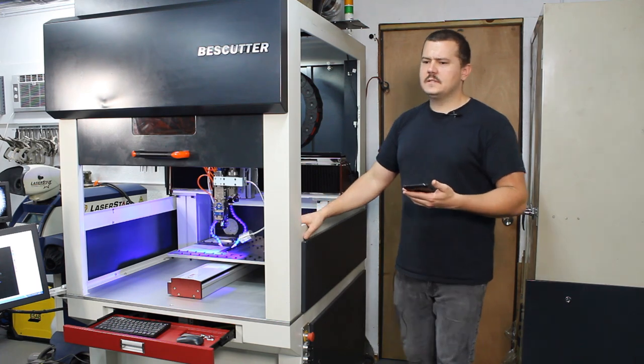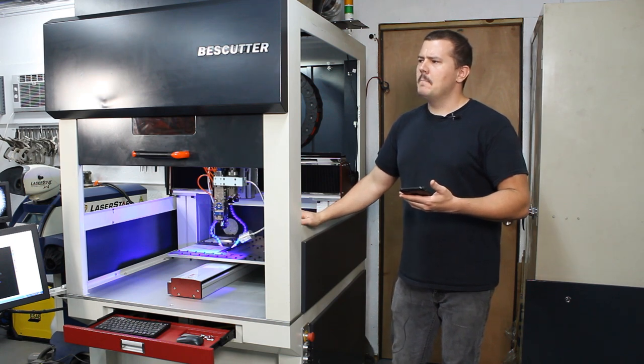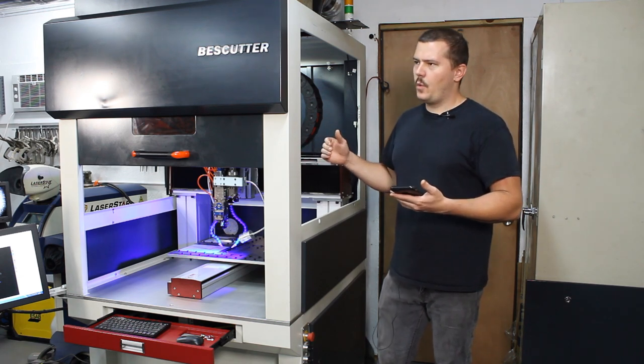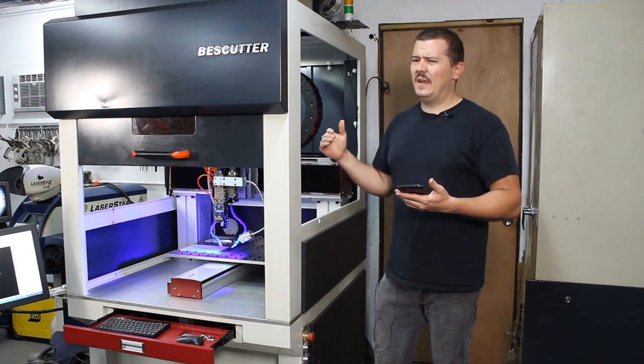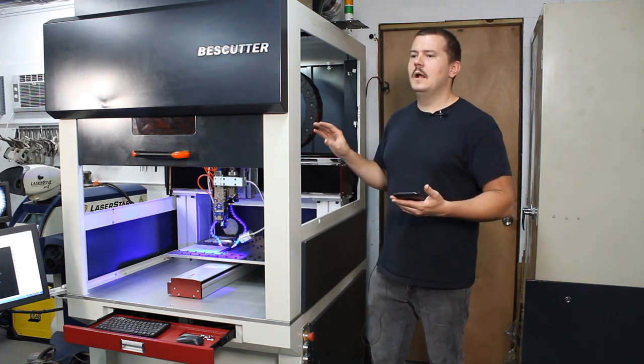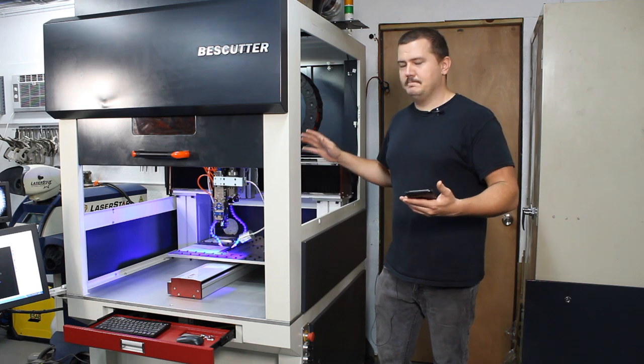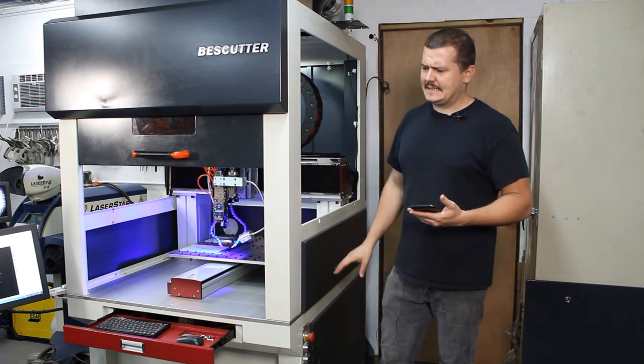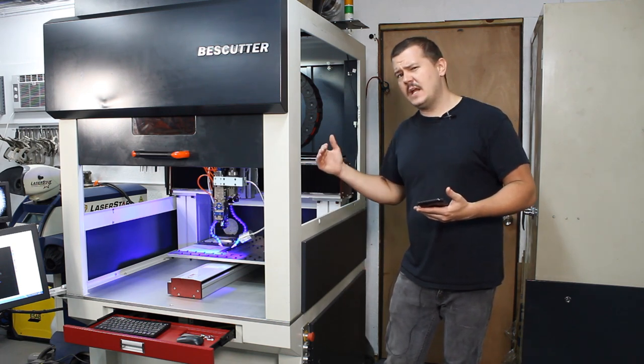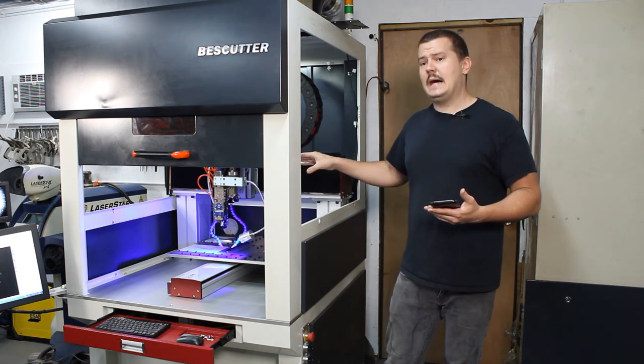Your power requirements, this draws about 25 amps. I believe that's at full load on the 240 volt American side of the buck transformer. So that's going to require at least a 30 amp breaker, if not a little bit larger. Talk to your electrician for hooking the machine up. It's not that much power. This unit is single phase, so you can run it anywhere in the U.S. This is very versatile. At the time I purchased this, the 750 watt unit was the biggest that they could go on single phase. That may have changed now. I have been seeing some 1,000 watt units handheld that are single phase, so that might be possible now.